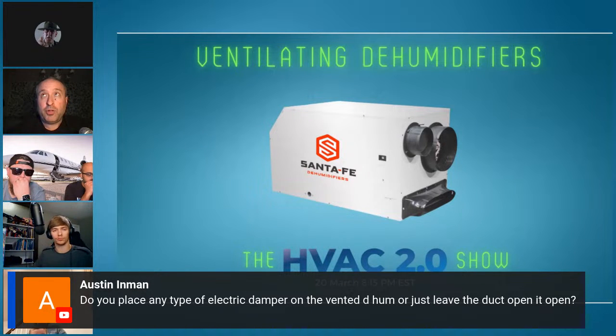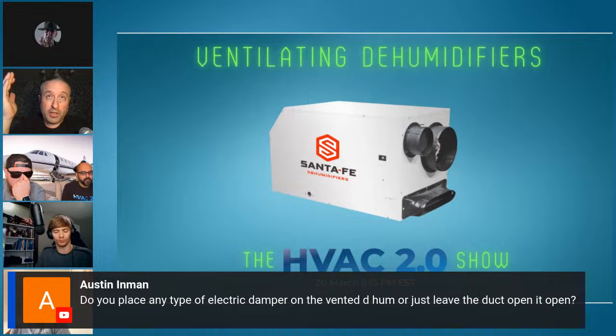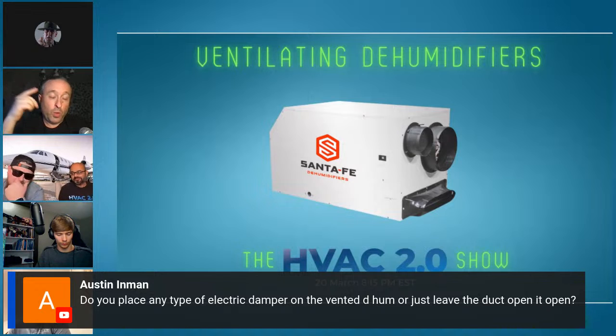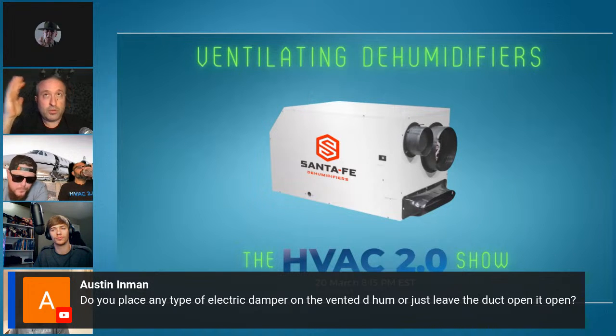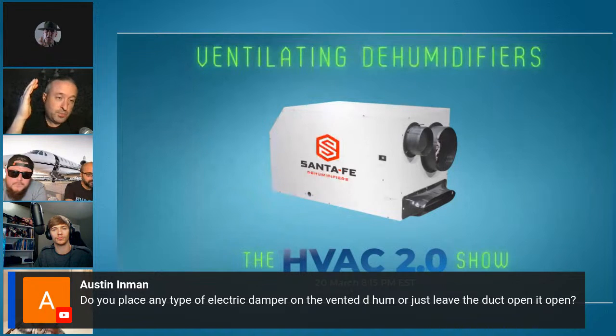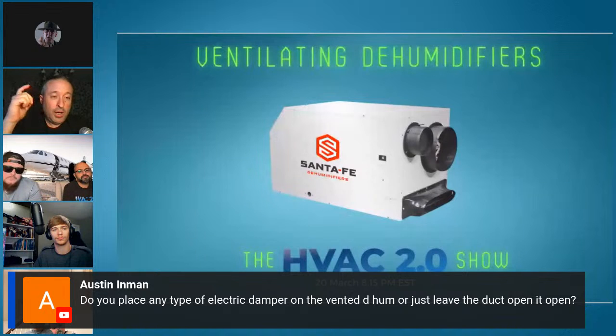But if you're sizing tightly, when a heat pump, or any system, is running on high because it's really cold out, that's when you're going to get the maximum outdoor air. I played with this on one client's house, and with the damper closing at 15 degrees, he was getting into resistance, so we closed it at 20 degrees instead and kept his system out of resistance because that extra load was enough to push him there. So yeah, there's extra load, and in the summertime it can be nice to close the damper when it's really hot or humid outside, so you aren't adding extra load.